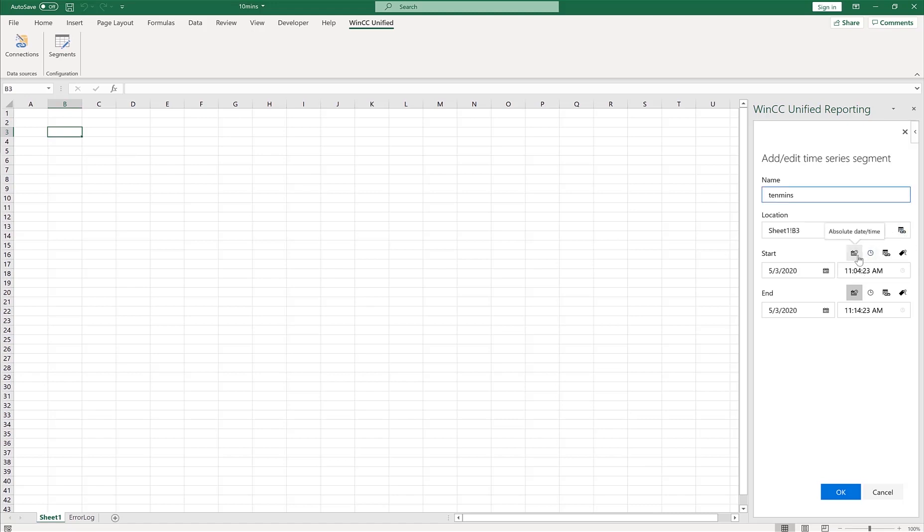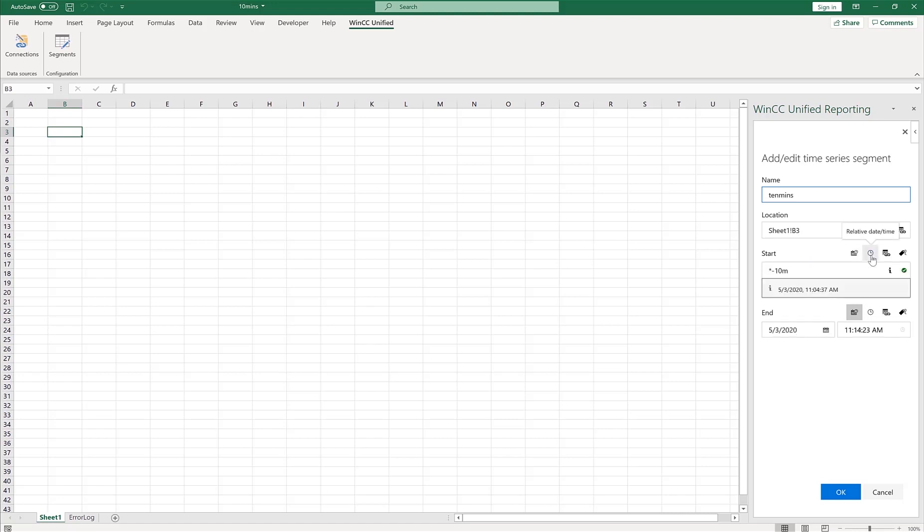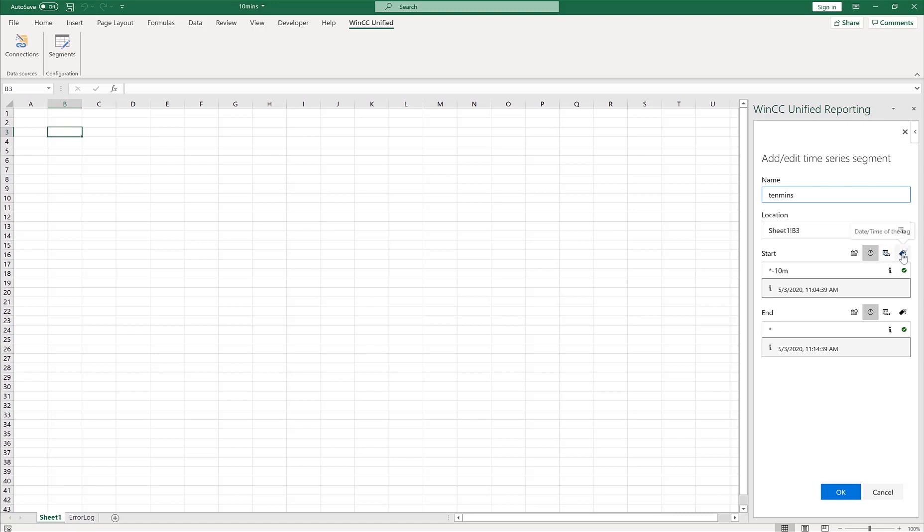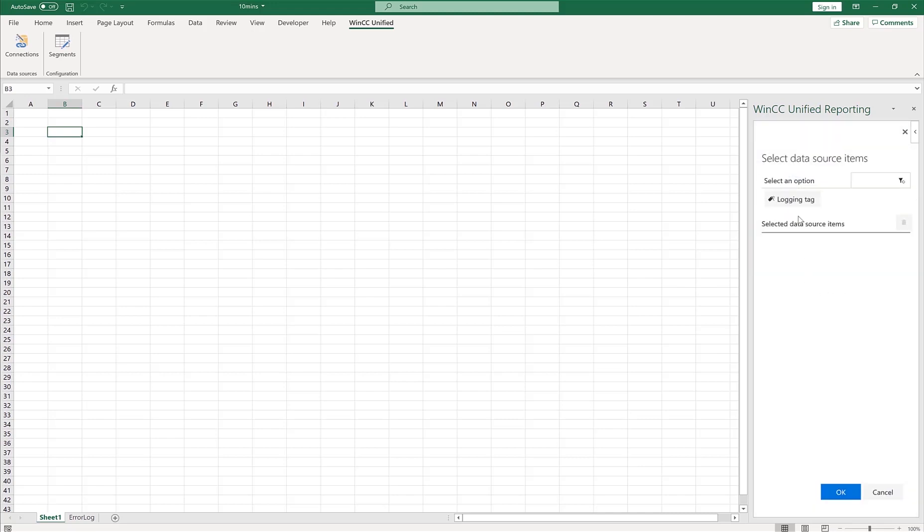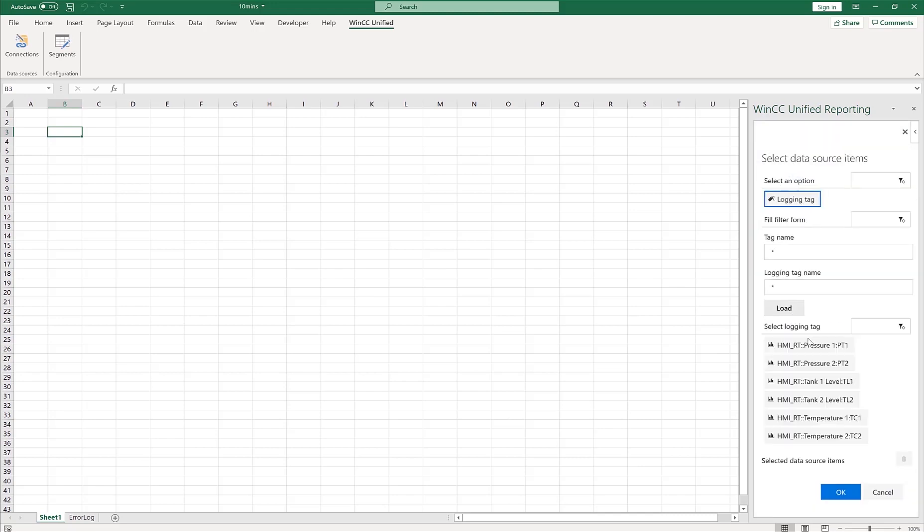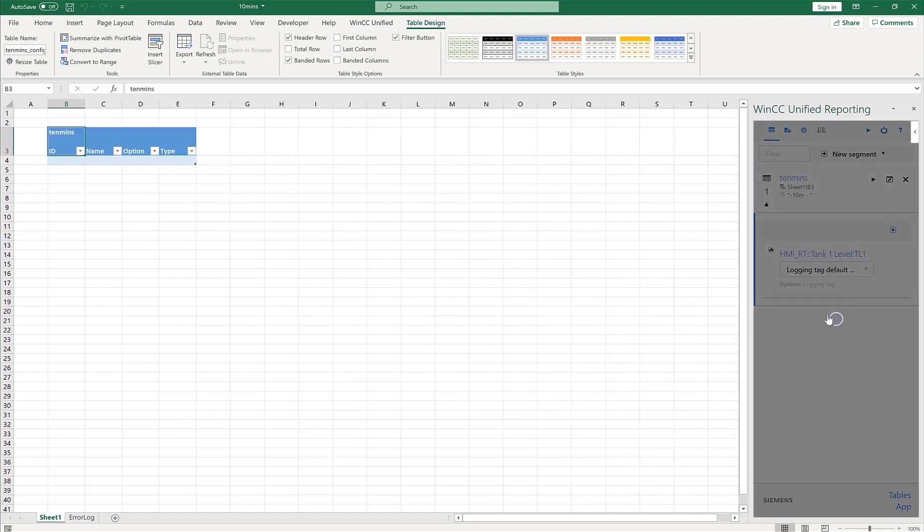We can say absolute date and time, so you can define it right here, or relative date and time, that's 10 minutes, or we can say date and time of the cell, or even tie it to the date and time of a tag in our runtime. For now let's just go ahead and see, last 10 minutes. I click the down arrow, I can add items, I'm going to select logging tags, load all the tags, and let's just say we want the tank level for now, hit okay.